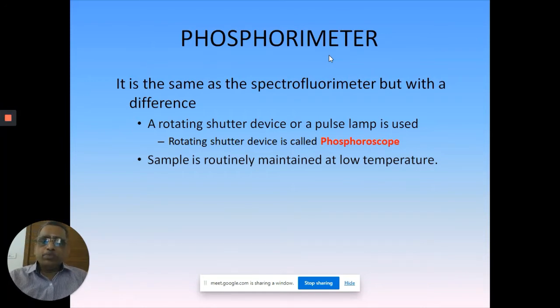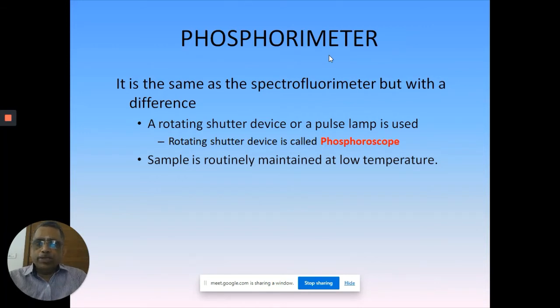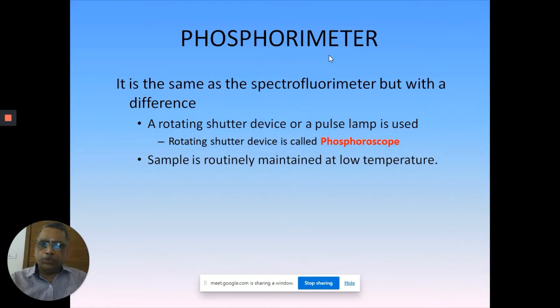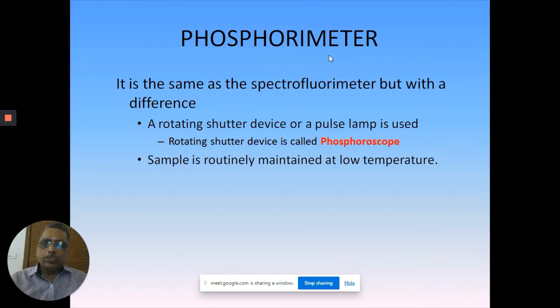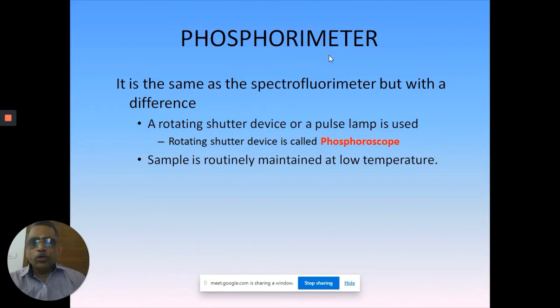If you look at fluorimeters, you will see two modes available: fluorescence mode and phosphorescence mode. When you switch to phosphorescence mode, these devices get activated. You have a rotating shutter - a mechanical shutter in front of the light source and also in front of the detector. This is called a rotating shutter, and this device is basically called a phosphoroscope.